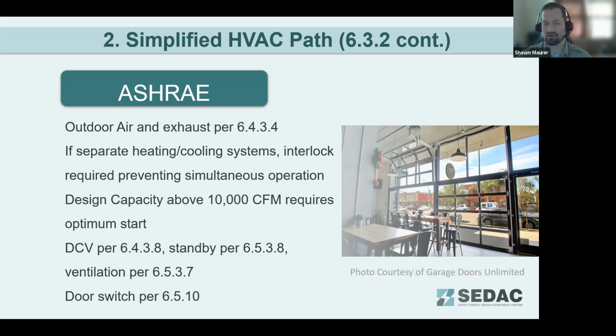We see this kind of frequently with restaurants. They have overhead doors for one of the walls so they can open up a patio-like area on mild days and have an open air seating area that they can then close off and make an interior part of the building when the weather's not as nice. Something important is if you're going to open up the system to open air, you don't want the HVAC system also running to try to condition that space, because it's just not going to be able to keep up. And that's what that door switch component requirement there is at the end of that.